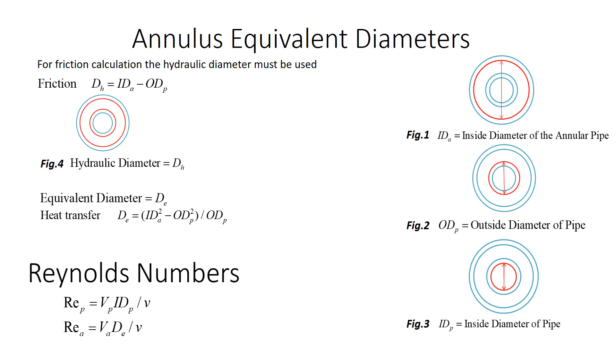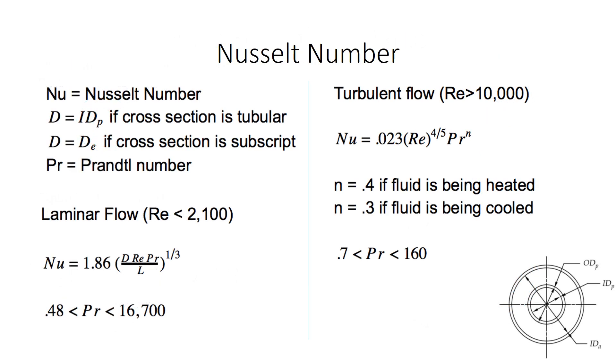After both diameters have been found, the hydraulic diameter must be used to find the Reynolds number for the pressure drop, and the equivalent diameter must be used to find the Reynolds number to find the Nusselt number. Once we calculate Reynolds numbers for the inner pipe's inner diameter and the double pipe effective diameter, we must determine the Nusselt number. If the system is laminar where Reynolds number is less than 2100, we can use the Nusselt number equation shown on the left-hand side of the screen.